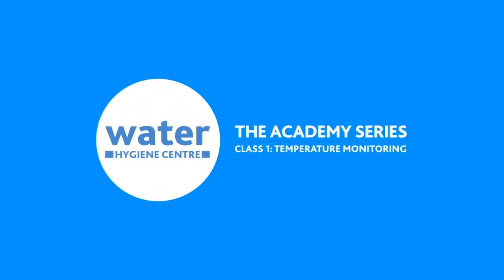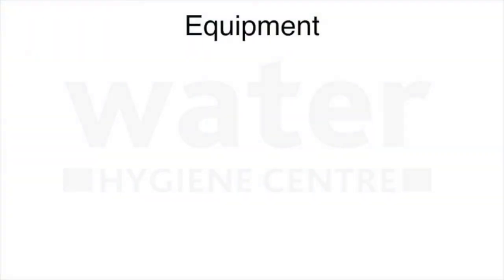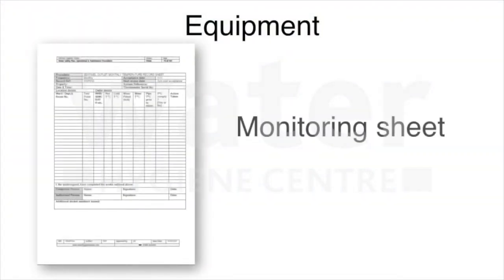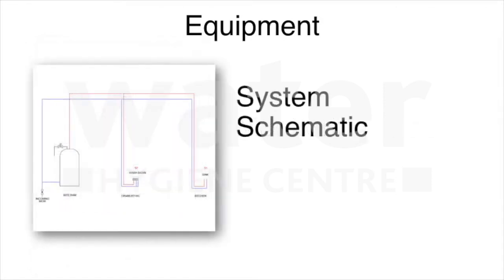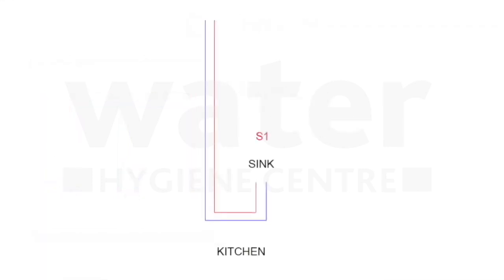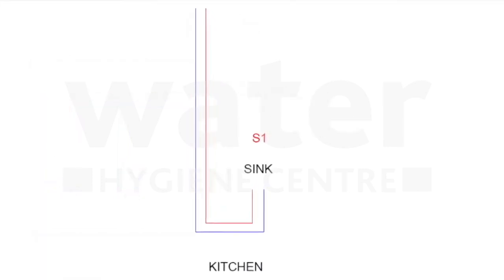This is Class 1, Temperature Monitoring. For temperature monitoring, you will require a monitoring sheet for recording all results and comments. Monitoring sheets should also include the name of the technician completing the monitoring and the identification number of the thermometer being used. A schematic of the water system showing all outlets and identifying which outlets to take temperatures from. These are known as sentinels. Sentinel 1 is shown on the schematic as a red S symbol.